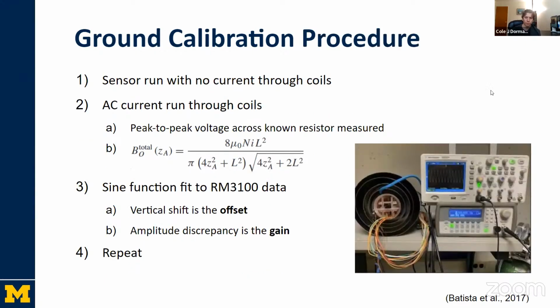So what's the ground calibration procedure? Here's a picture of the setup, where the sensor is run with no current through the coils in order to find the zero level offset, or background field of the sensor. Then an alternating current is run through the coils, and using this oscilloscope we can find the peak-to-peak voltage across the known resistor. The current is a function of voltage and resistance, and the total magnetic field amplitude of this AC magnetic field is given by this equation. A sine function is fit to the data measured from the RM3100, and the vertical shift above zero is the offset of the sensor.